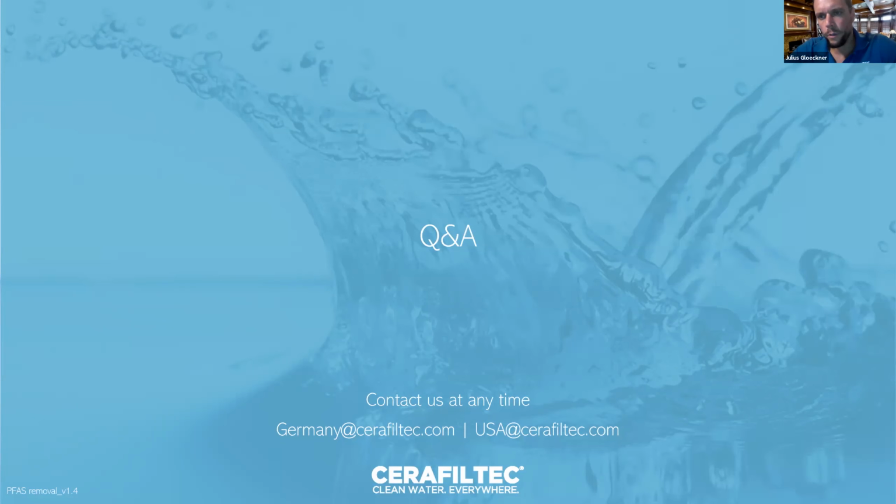Yeah, maybe to highlight one quick addition to Chris's question there on the PFAS process and the incineration and removal and so on. Just to explain at a high level, maybe, the process: after a backwash, we remove the layer, we bring a new layer on the membrane, and we do this every filtration cycle. So we bring the layer on the membrane, we filter for about 12 hours. This is all calculated depending on what's in the water and what we want to actually remove. And we also calculate how much powder activated carbon we must bring onto the membrane layer until the powder activated carbon reaches its adsorption, is fully saturated, right? And when it's fully saturated, then we bring a new layer on.